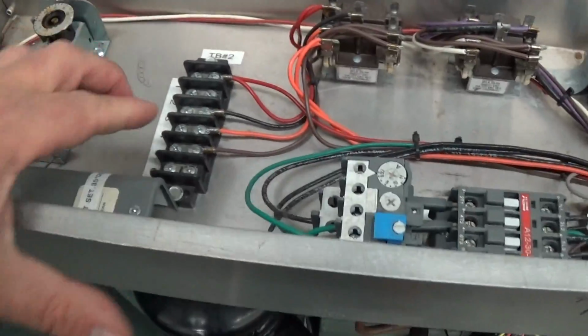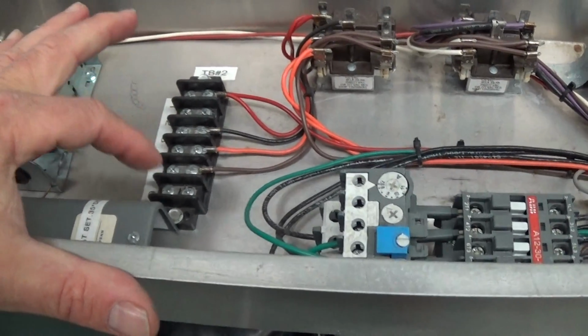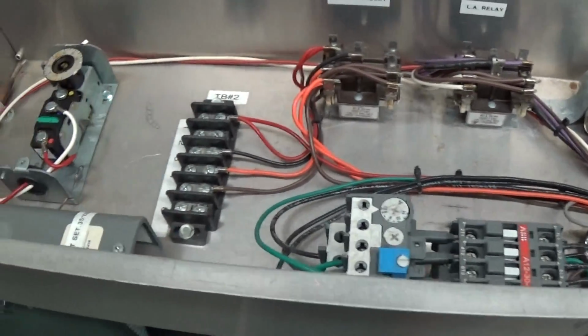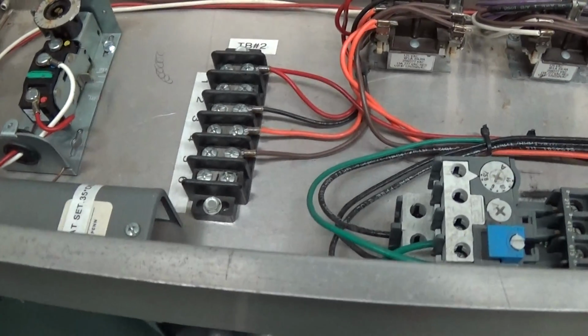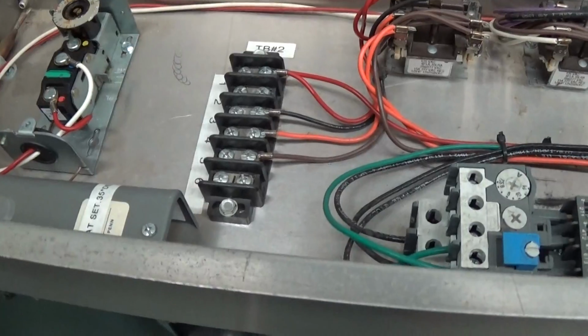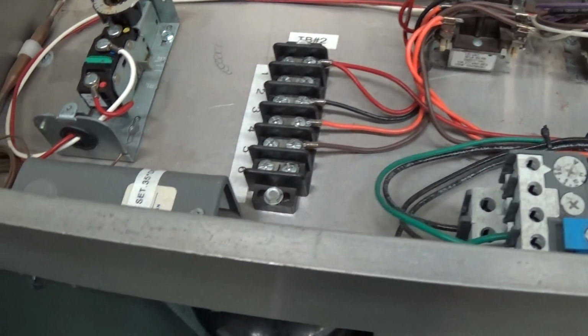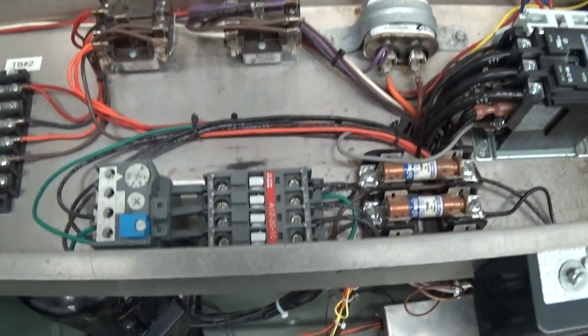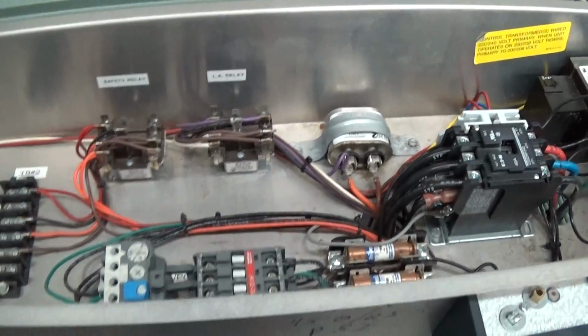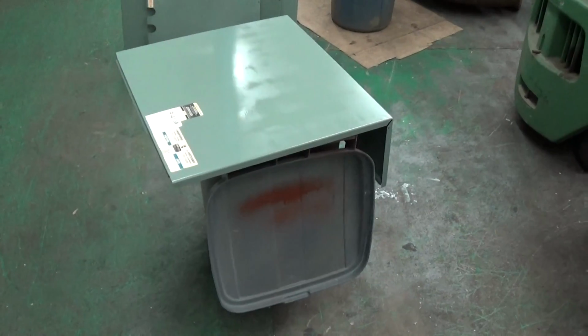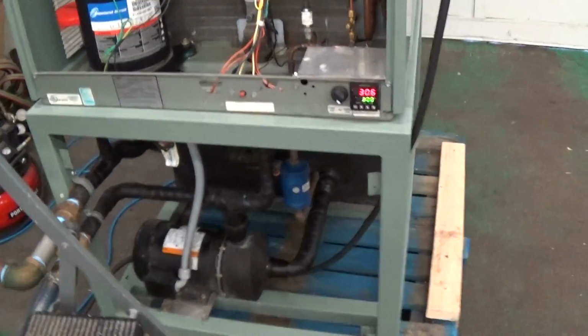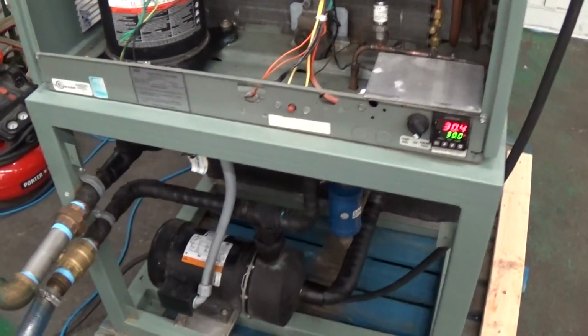Nothing else in here. This terminal block here is for if you have the remote start-stop module. It is something you can order from Cold Shot Chillers if you'd like. Then you just have your main fan pump relay and your main contactor capacitor for your fan motor in here too. This is all covered by that cover right there, which, as we mentioned to the customer, did get repainted, and the prior weird logos from the yogurt shop it was at were removed.